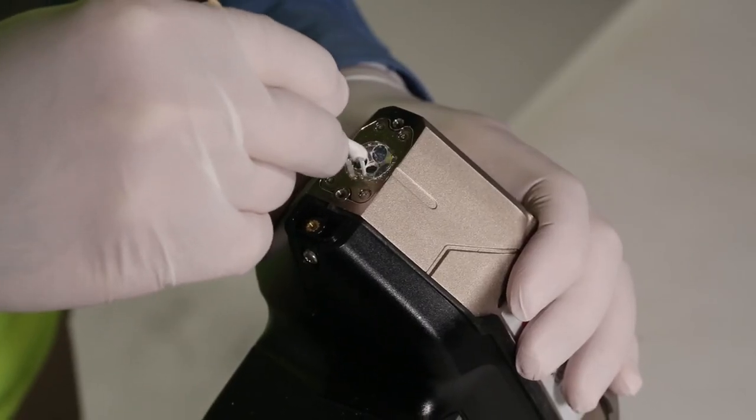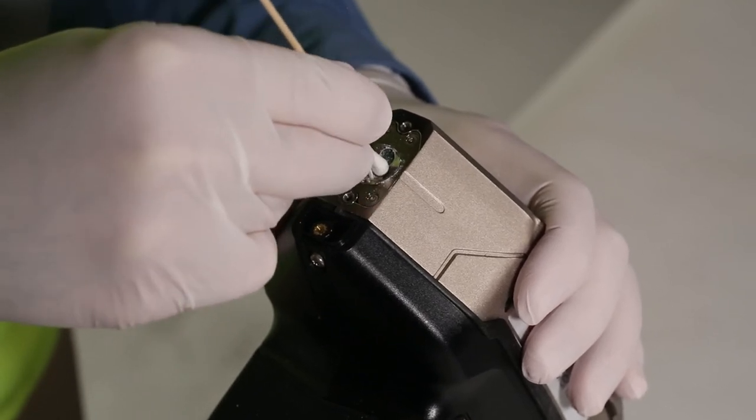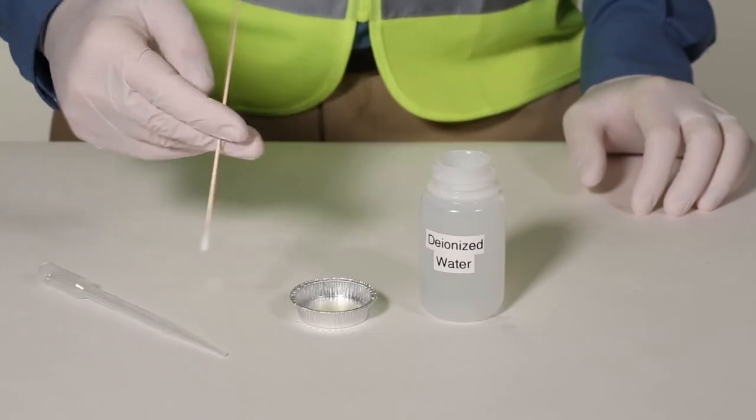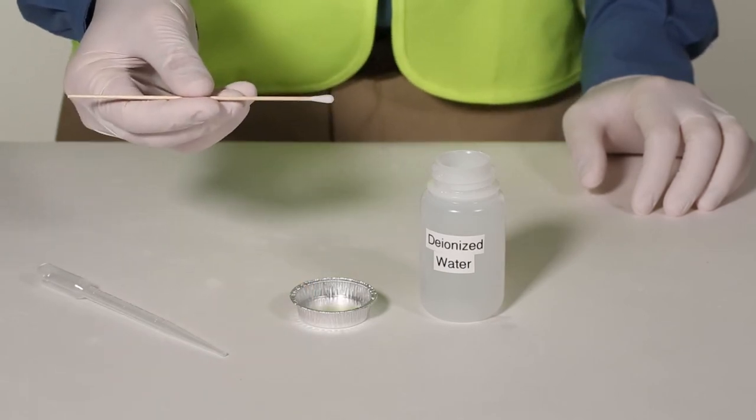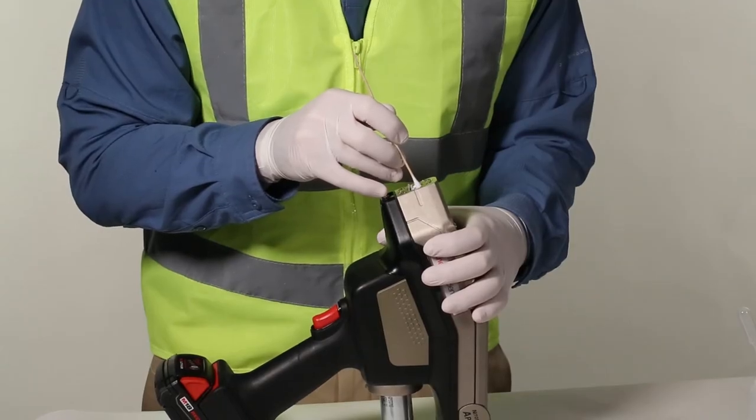Clear any loose or dry cleaning mixture from the sample chamber by using a dry cotton swab. Proceed by dipping a new cotton swab into a small amount of deionized or distilled water and remove any cleaning mixture from the sample chamber.